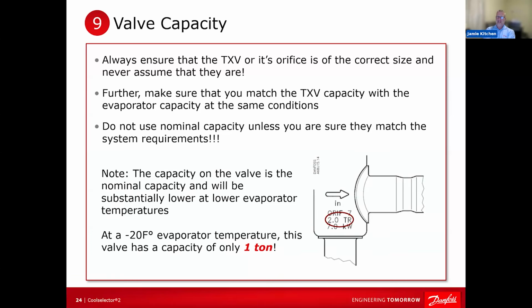So we all make mistakes. Engineers make mistakes. Manufacturers make mistakes. And one of the easiest and most common mistakes is what I just explained here: nominal capacity versus application capacity. Again, one of the mistakes I see from people who are not used to refrigeration, and I think it's hard, is that the evaporator temperature difference trips them up. And we've all made that mistake.